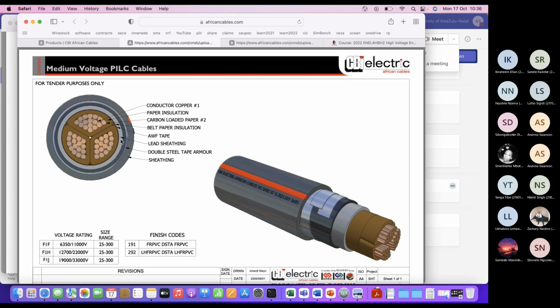Then around those 3 phases is lead sheathing. Right. So within all of that goes the oil. So it's not just paper, it's paper and oil. Right, so it's a combination of liquid and paper, liquid and solid. And then outside of it, it has some armoring so that if you're trying to dig into it, you find it difficult to break. Environmental elements will find it difficult to get through. On the outside, there's another cover, just PVC sheathing. Right, so that's a PILC cable.